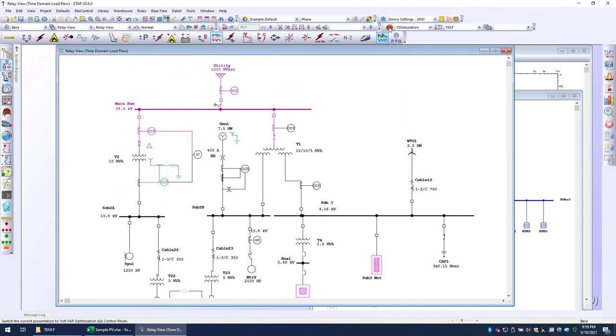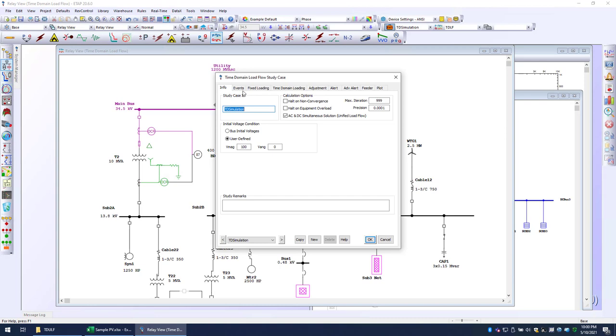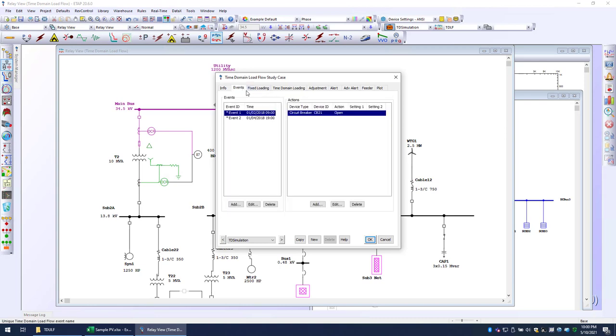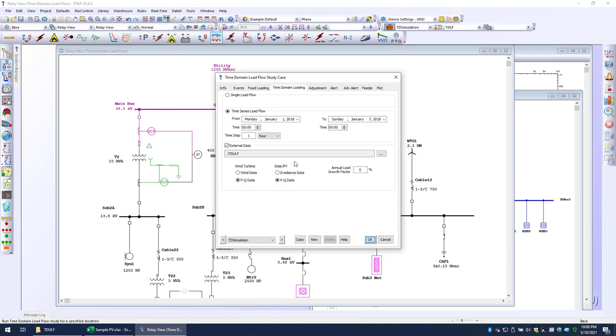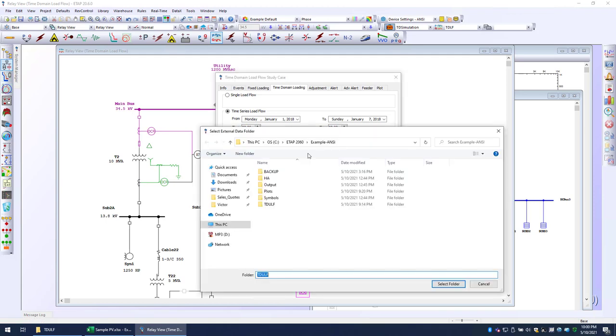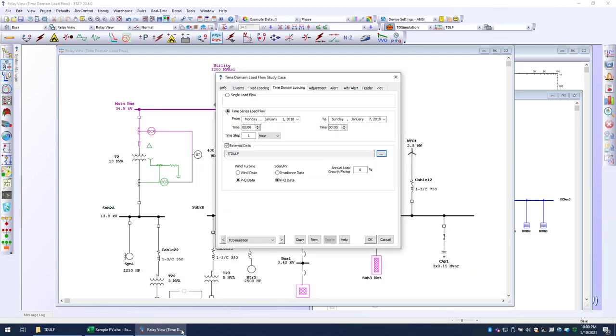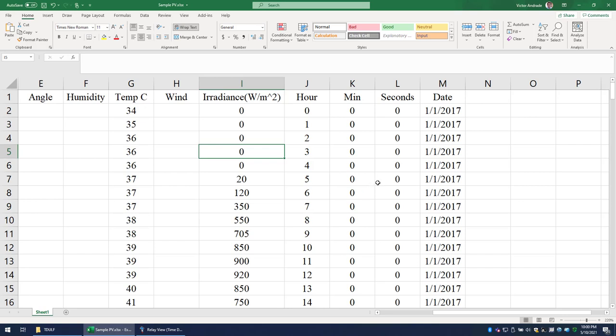So let's go ahead and look at the study case for time domain load flow. You'll notice that you're able to include events such as on January 2nd, we're going to open a circuit breaker. And then 2 days later on January 4th, we're going to do a load impact of 50% to lump number two. Most importantly, it allows you to select the time series load flow time period from and to, and it provides you with a path folder where you could select where the source and loading information over time is saved.